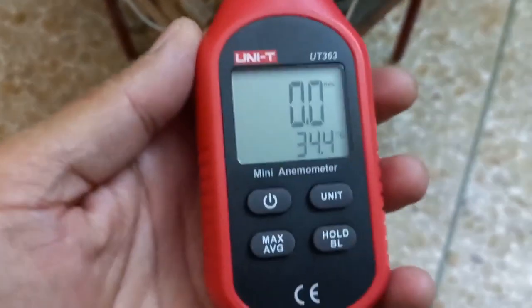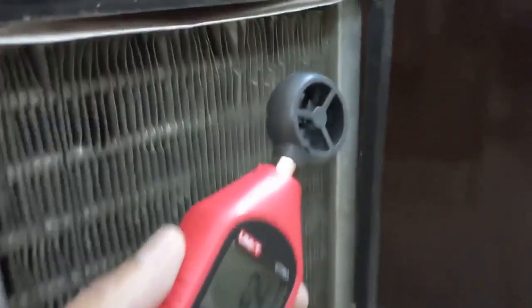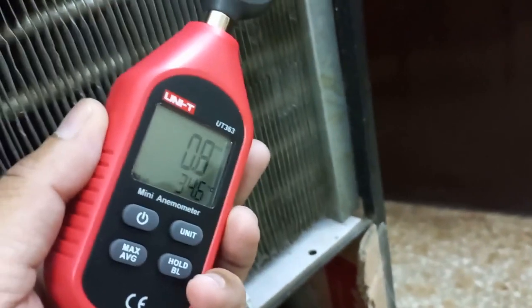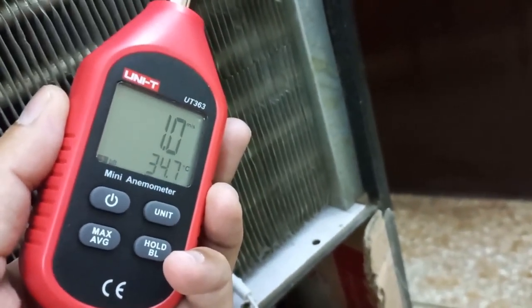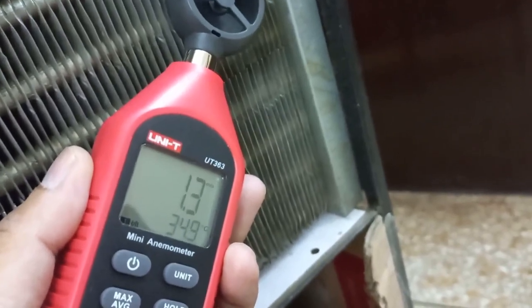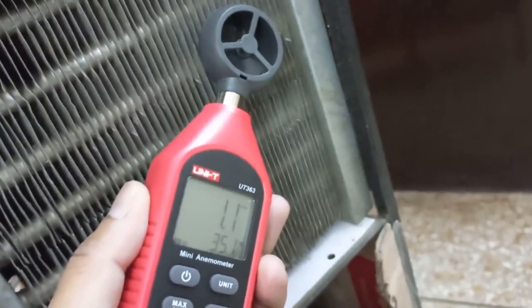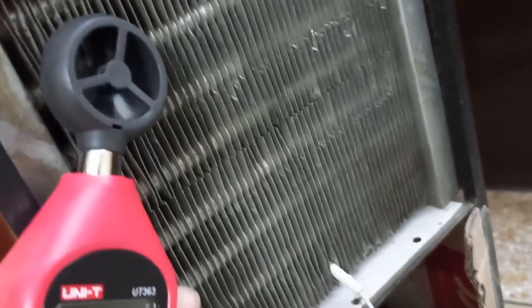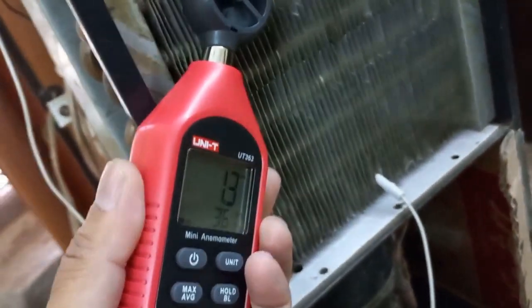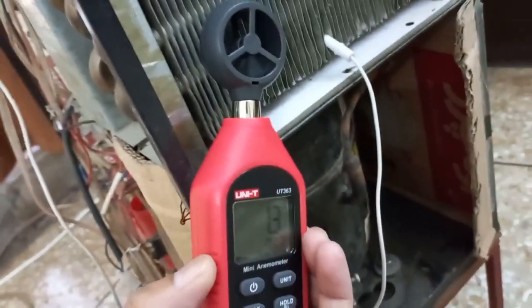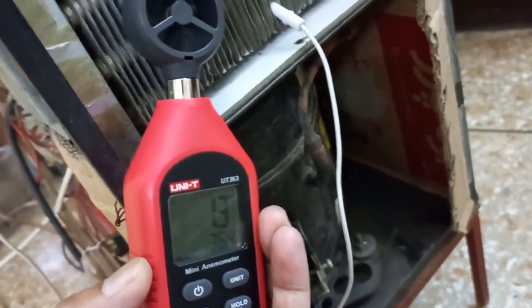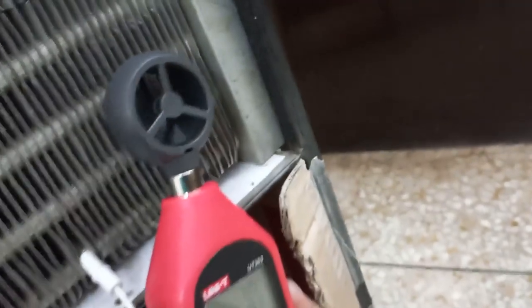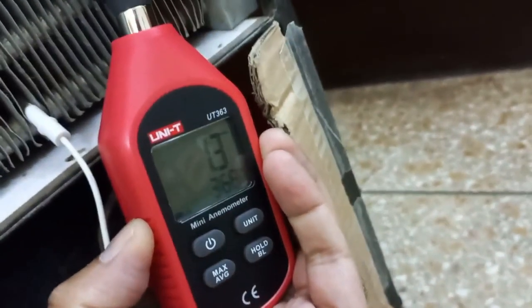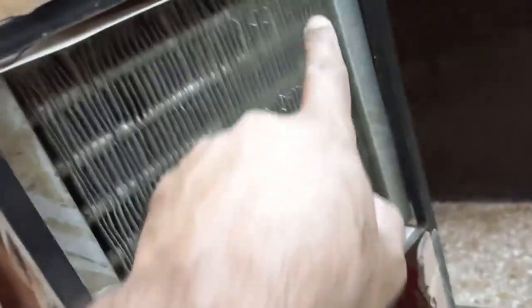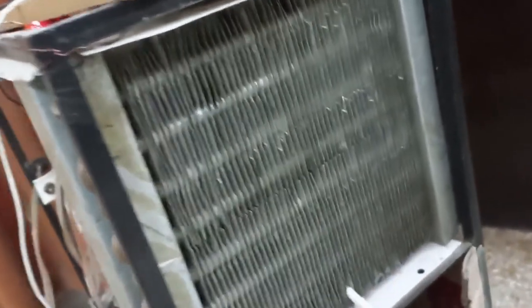If I check the flow rate passing through this condenser, for that I have this meter, and now if I put this meter here, it's showing 1.0 or 1.1 meter per second, 1.3 meter per second. This side, again 1.3 meter per second. This side, same, 1.1 or 1.3 meter per second. And at this fourth corner, 1.3. Same air is passing through all four corners, 1.2 or 1.3 meter per second.